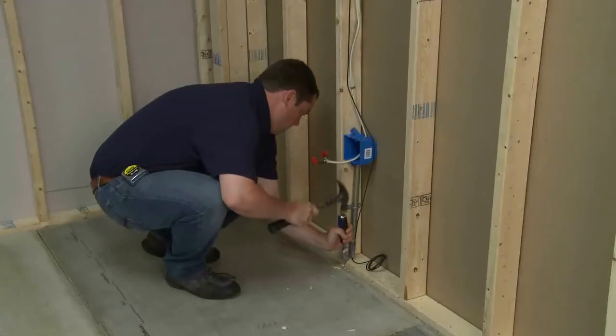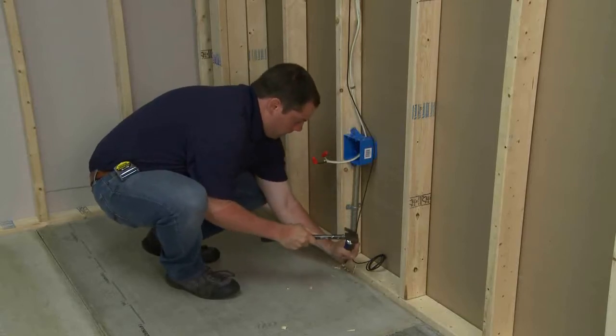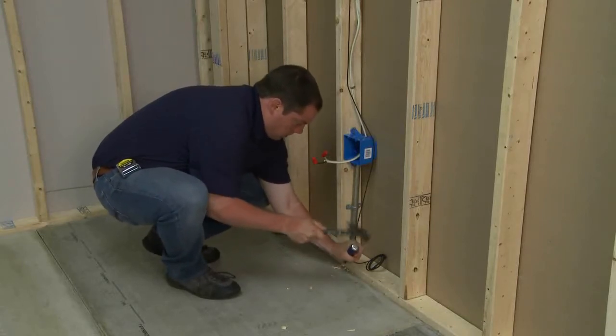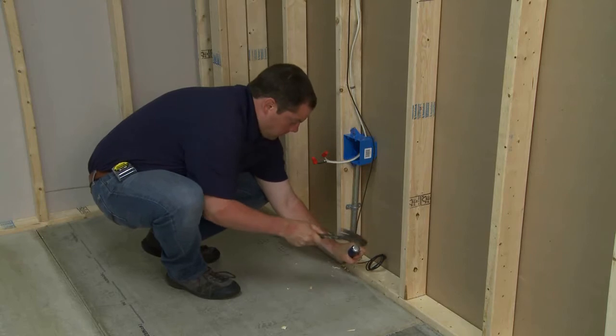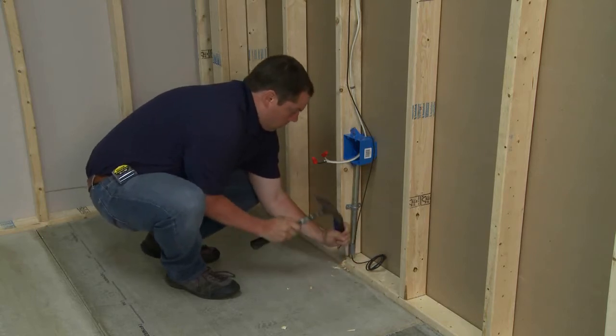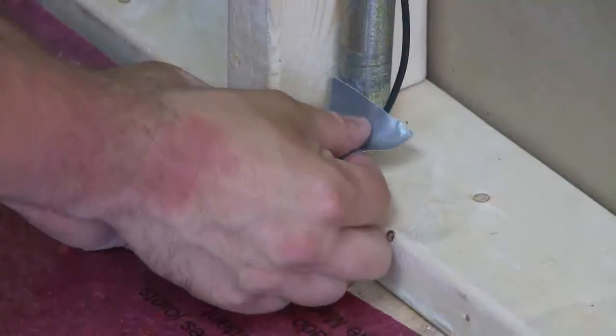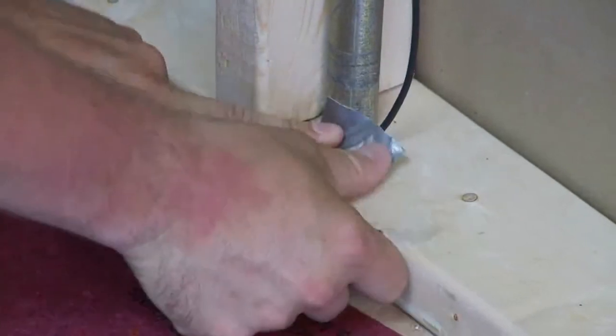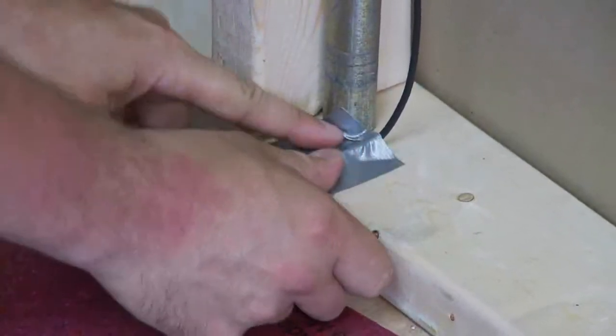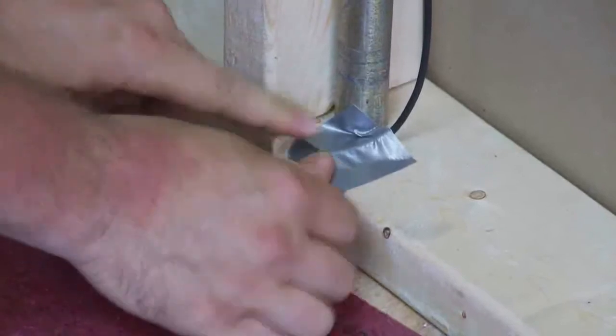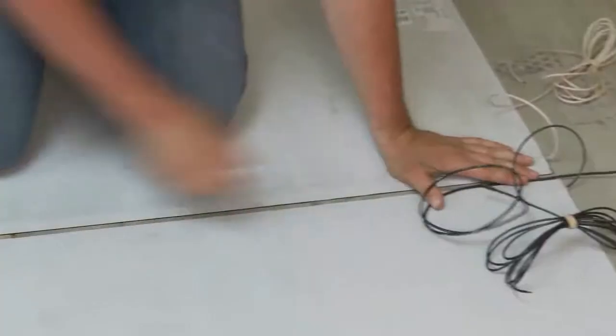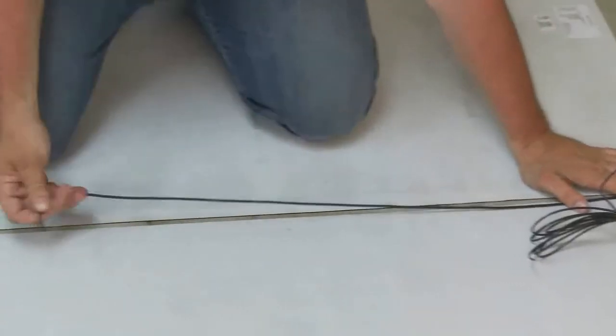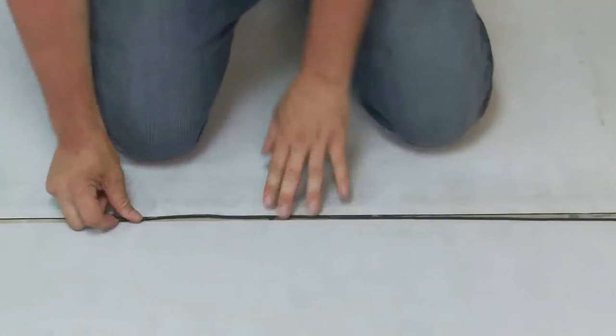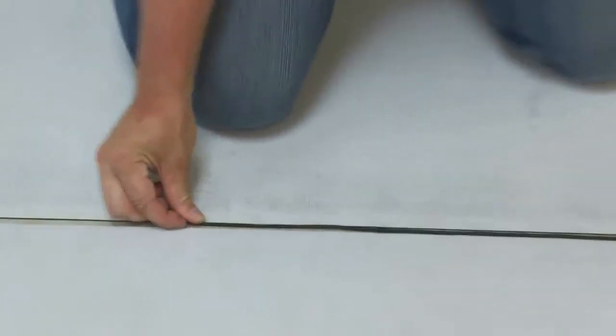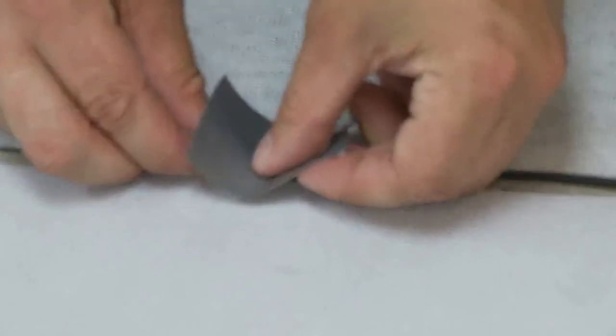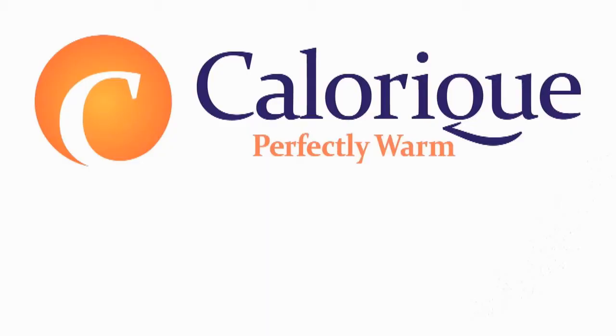If thin setting over backboard or slab, saw a groove to recess the sensor to the level of the mat. The sensor probe can be held in position within the groove with a small amount of tape. The sensor should extend approximately 6 inches to 12 inches from the wall adjacent to the mat shown and must be level with the mat.